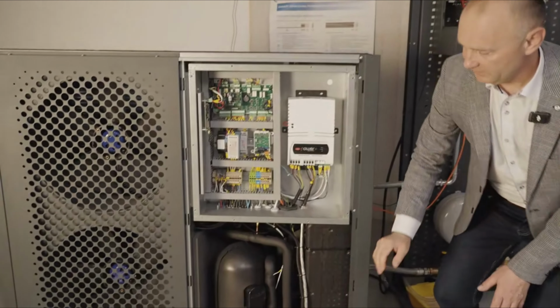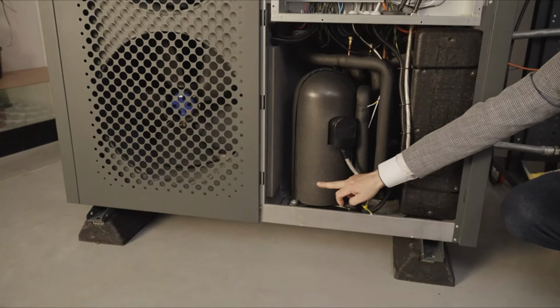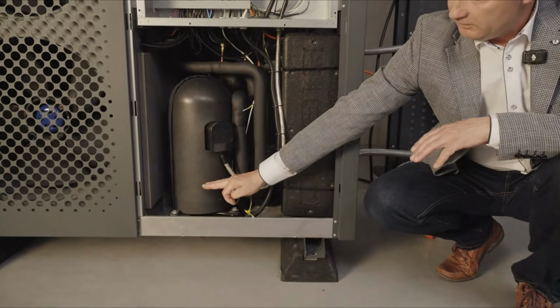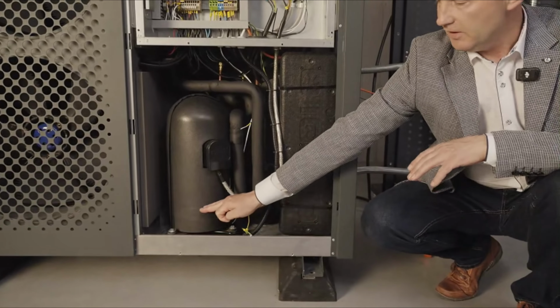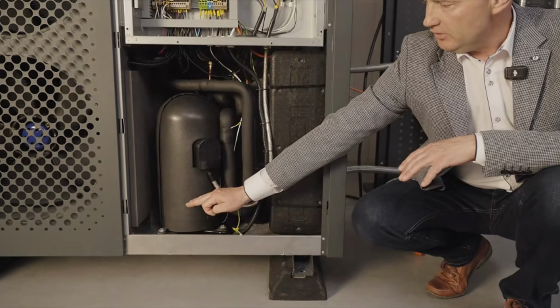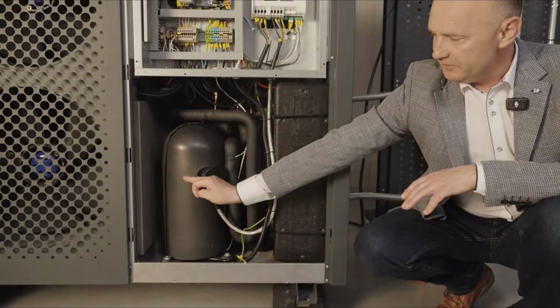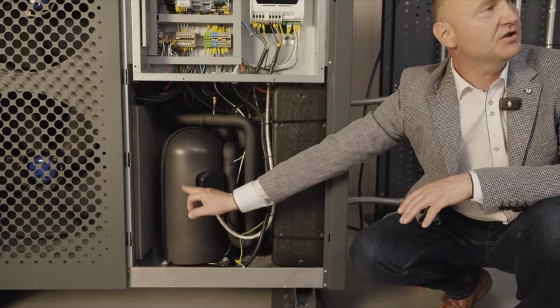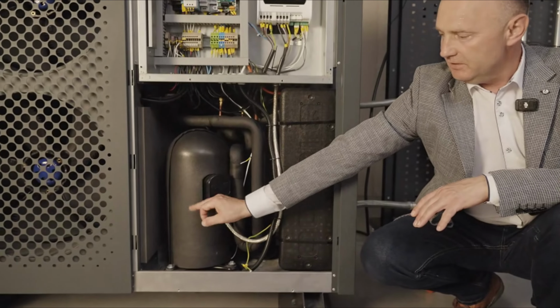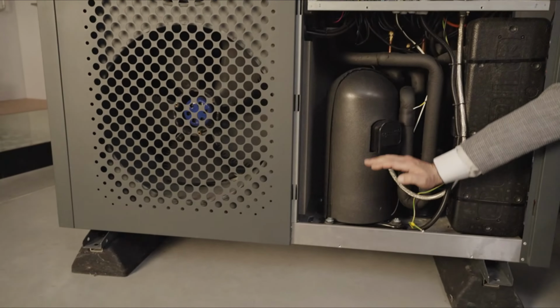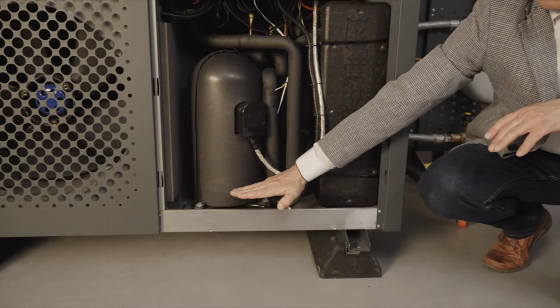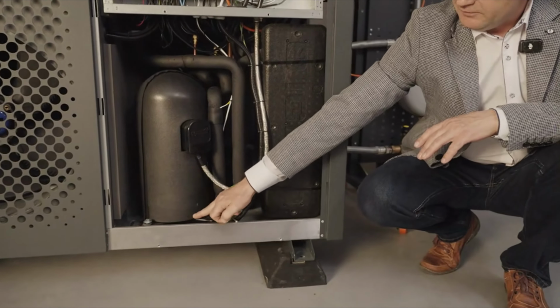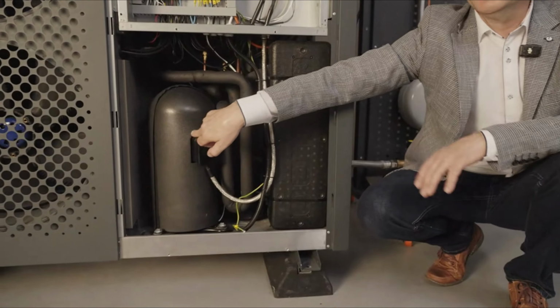Well, it's constructed in such a way that within this compressor, at a specific height, there's an oil level. Here at the bottom, in the casing, we have oil that lubricates it. And now above this oil, in this specific compressor design, we have high discharge pressures. As a result, the oil is pushed down by these pressures. This top cushion hydraulically forces the oil downwards and into channels that lubricate the entire compressor.